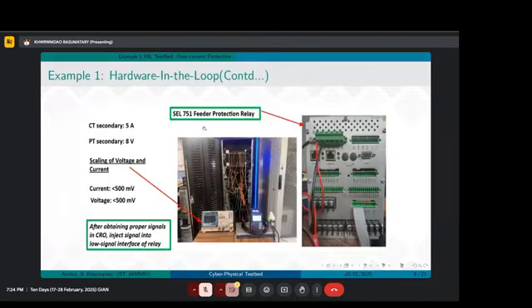That is the validation. As I mentioned, before injecting the signal into the relay, you first need to test it coming out from the GTAO card, and the signal should be less than 500 millivolts in voltage and current, because you have to scale down the signal. After obtaining the proper signal, you need to inject it into the low signal interface of the relay via a flat ribbon cable, which is a 14-pin ribbon cable, as you see here.